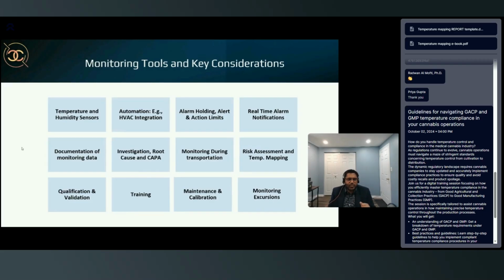I have seen, and I think I mentioned, multiple times humidity increasing suddenly during the night as temperature drops. On colder nights, as the temperature goes down, humidity spikes up. There's an inverse relationship, and I see that during the night. Fortunately, we do not have any growing happening, or people present, during that period of time. But it is important to manage temperature and humidity 24 hours, and at least that excursion will help you. But if you're in the GMP environment and do not have people, or you're not processing anything, like you're not packing at night in most places, and your temperature drops to 15 degrees Celsius, that's fine because you don't have any cannabis in there.